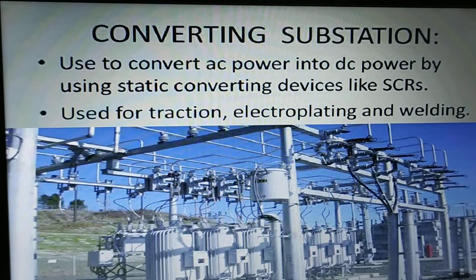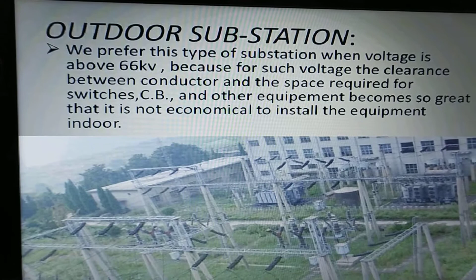Next, based on the design consideration, we will be studying the constructional features and how different types of substations are used. This type is the outdoor substation. Wherever the voltage level is beyond 66 kilovolt, such substations are constructed. It consists of many equipments, controlling mechanisms, and protective mechanisms, and the transformer is also installed in open area. For such a substation, clearance is required, so more space is needed. Generally they are located in the load centers.